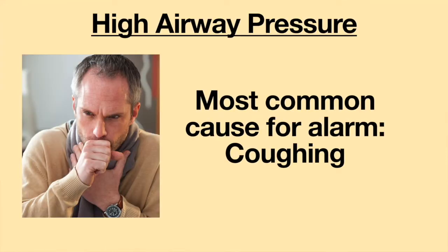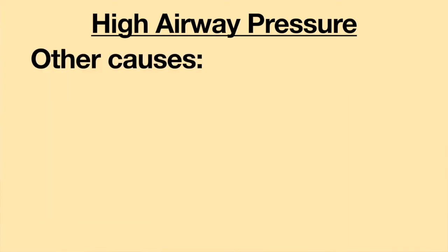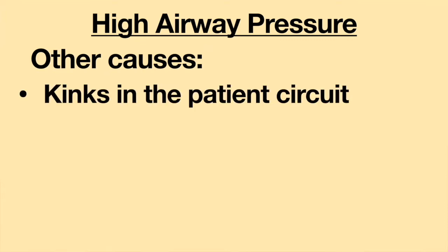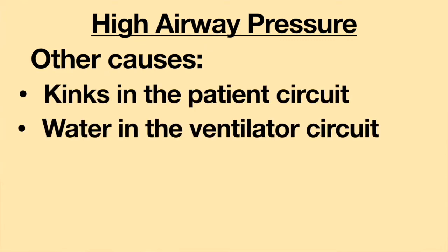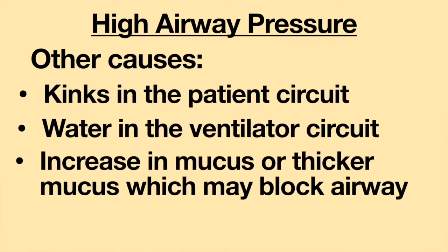The most common cause of a high airway pressure alarm is the spike in airway pressure produced when a patient coughs. This is almost always self-limited and requires no intervention. Other causes of high airway pressure include kinks in the patient circuit, water in the ventilator circuit, an increase in mucus or thicker mucus which may block the airway, and gagging.